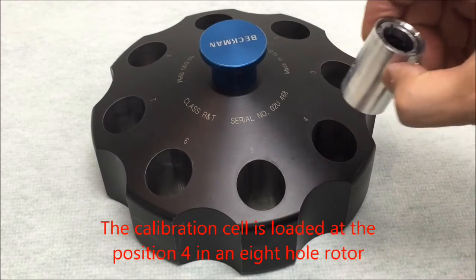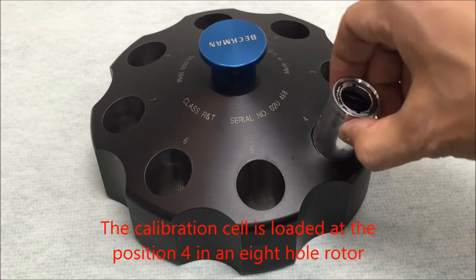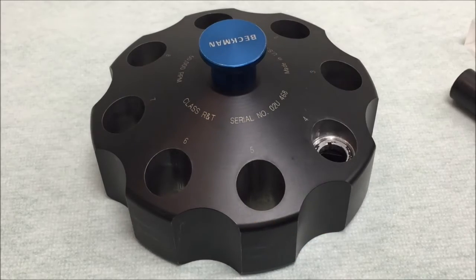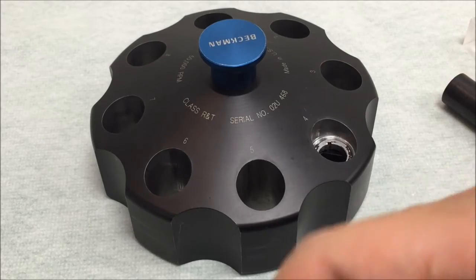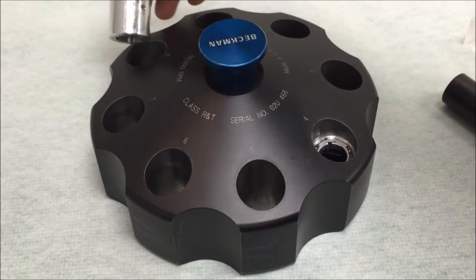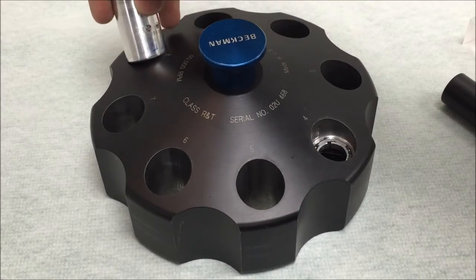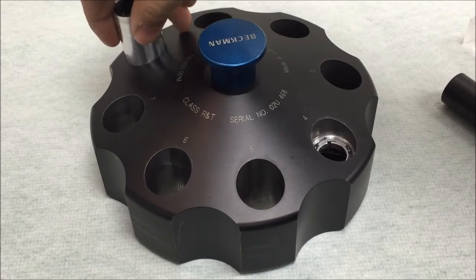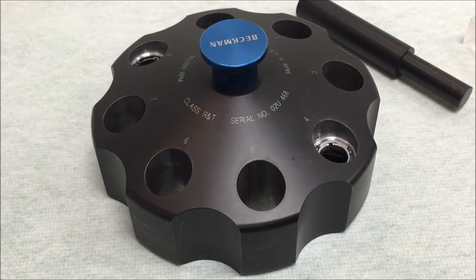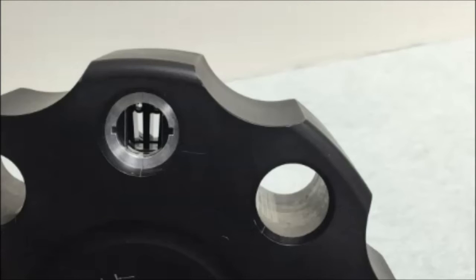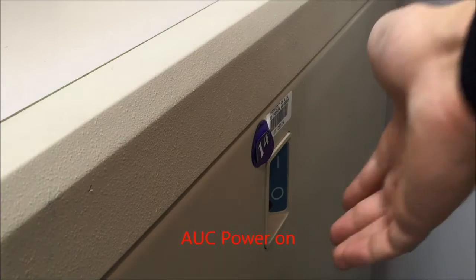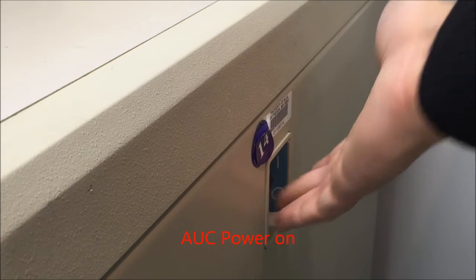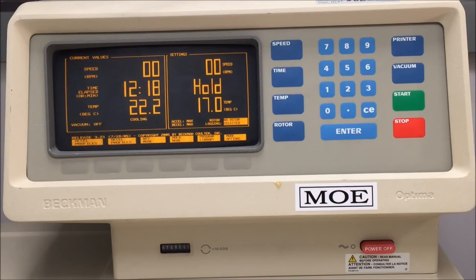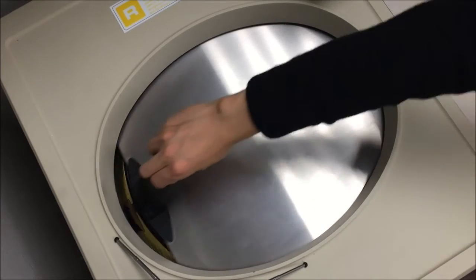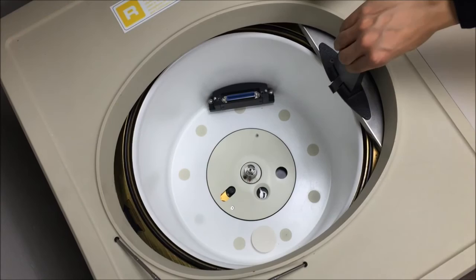Load the cells into the rotor with screws facing the center of the rotor. From the back of the rotor, align the cell's marker with the rotor's marker. Power on the AUC. Place the rotor in the drive of the AUC.